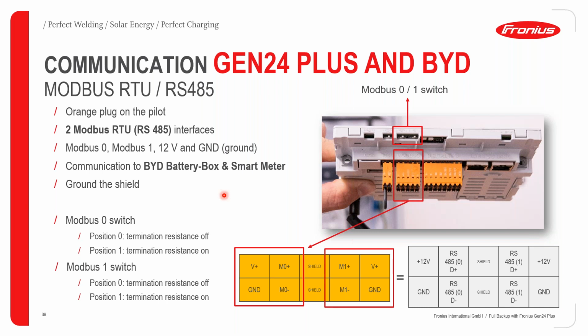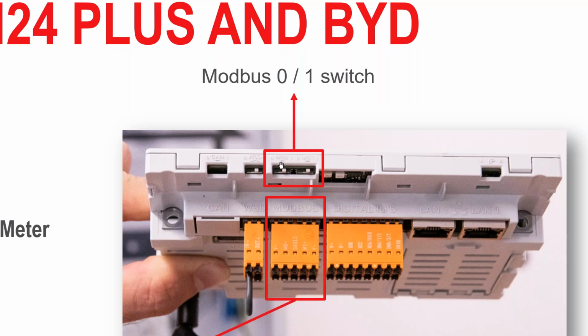Now talking about the communication connections between the GEN24 Plus and the BYD. Of course, we have modbus terminals. So for the pilot, as contrary to what we have in the snap inverter, we have two modbus terminals or ports, as we can see. And please ensure that these modbus switches are turned on. In order to make this clear, I'm going to see if I can zoom in a bit. Great. As we can see here, we have two modbus port switches. They are here, MB0 and MB1. So MB0 basically stands for modbus 0 and then modbus 1. So please ensure that the switches are on position 1.